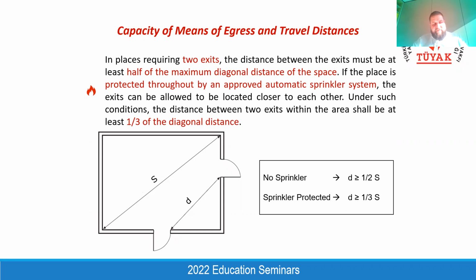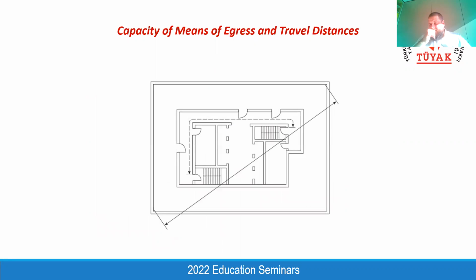In some situations, for example, when you are designing a shopping mall, you can only provide these remote, alternatively located doors on the facade of the subject unit, and the facade is really limited. In shopping malls, you have a facade and you have a very long width through the service corridors. That's why having a sprinkler system gives you the chance to make these remotely located doors close to each other. If you don't have a sprinkler system, the design may be locked. Maybe you cannot execute the process design due to the lack of area, due to the lack of facade to provide these additional doors. That's why it's important to know the advantages of the sprinkler system on the remoteness criteria as well. And also, it directly affects the locations of the staircase as well.